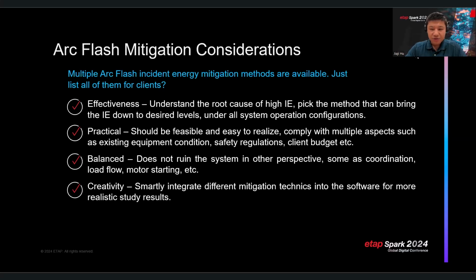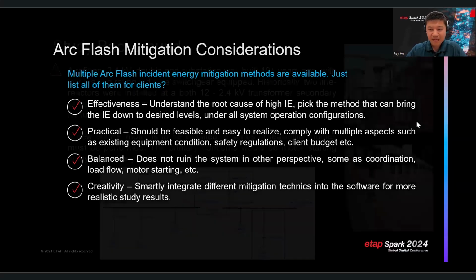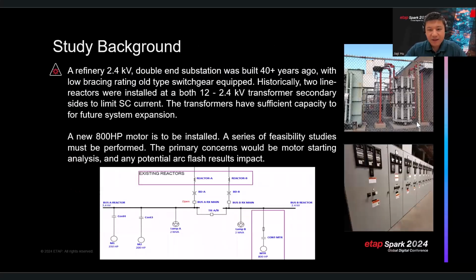So here we happen to recently done a project that is a perfect example of mixing all these considerations. So here's the project background. A refinery client has a 2.4 kV double-ended substation, which was built a long time ago with old type switchgear. The switchgear has a very low bracing rating. So historically, there are two line reactors installed at the 12 to 2.4 kV transformer secondary side to limit the short circuit current into the substation.